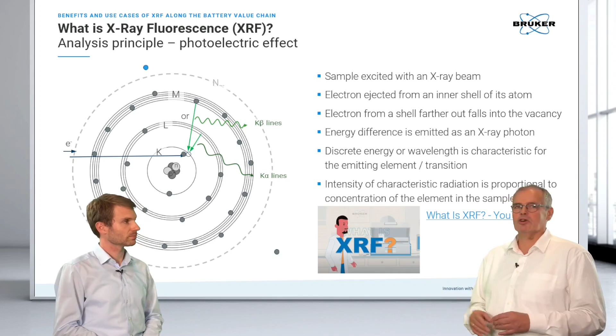Yeah, actually every XRF system looks a little bit similar. We have an X-ray tube which excites the sample, and then we have an outcoming fluorescence beam which enters the goniometer. There is also a technology with a semiconductor detector, called energy dispersive. This is on the detector side a little bit easier. Nevertheless, the S6 Jaguar is very compact. It's a benchtop instrument, but has the advanced technology of wavelength dispersive XRF.